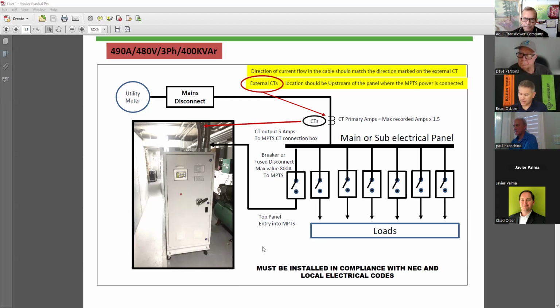Correct. Now, a lot of CTs that I've encountered do not come with shielding. Is it recommended by you that you get a CT that does have shielding, because the integrator actually allows a terminal for that shield? Actually, it's just a protection for the integrator kit, because if your integrator has enough static energy and doesn't have a ground wire, then you could lose your integrator kit. And if you lose the integrator, then you lose the power management data. And if you lose the power management data, MPTS doesn't know what to do because everything is reliant on the data supplied to the MPTS.